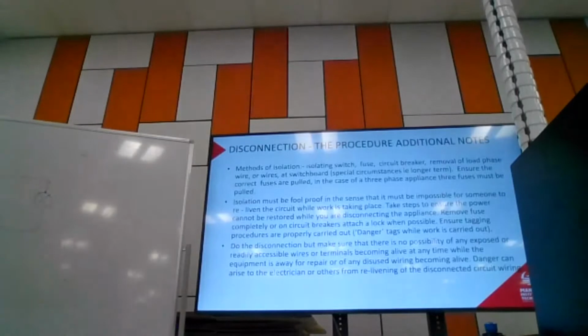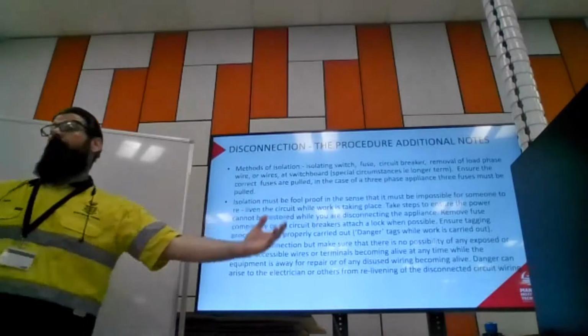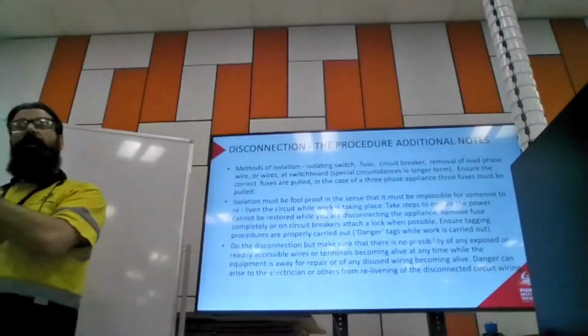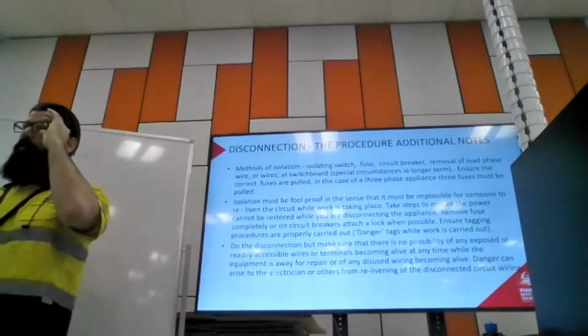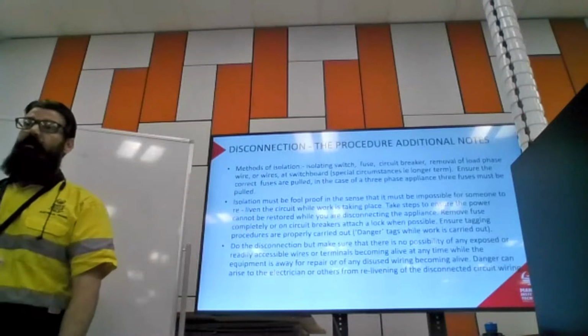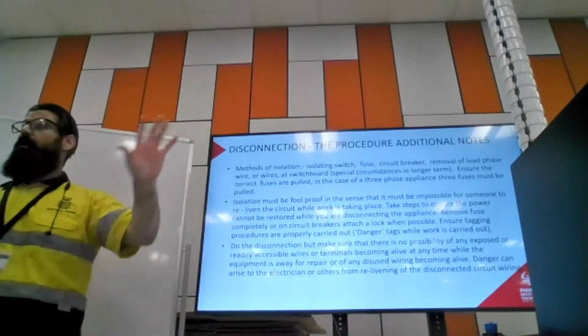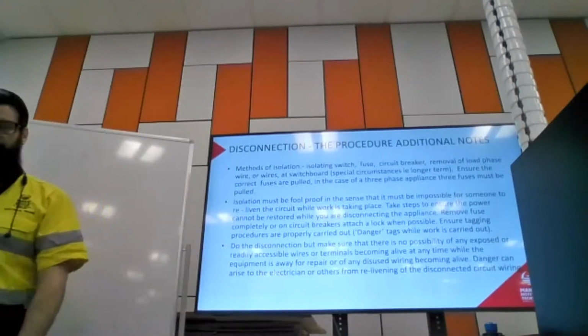Do the disconnection, but make sure there is no possibility of any exposed or readily accessible wires or terminals becoming alive at any time while the equipment is away for repair, or of any disused wiring becoming alive. Danger can arise to the electrician or others from relivening the disconnected circuit wiring. So if we're working on a fixed wired appliance and we disconnect it completely, and even maybe remove that appliance to be repaired elsewhere, we need to make sure that what is left behind remains safe.